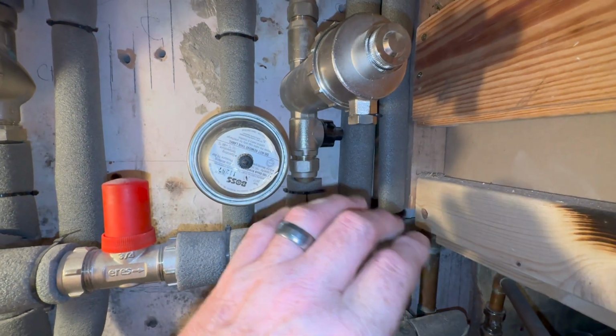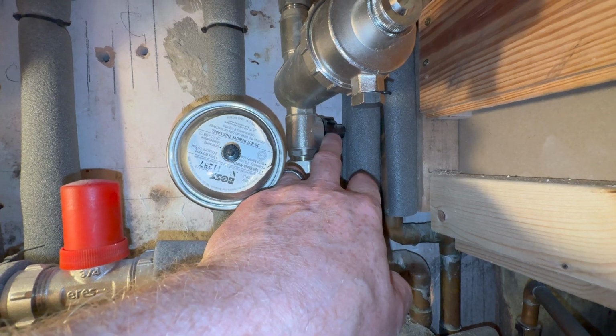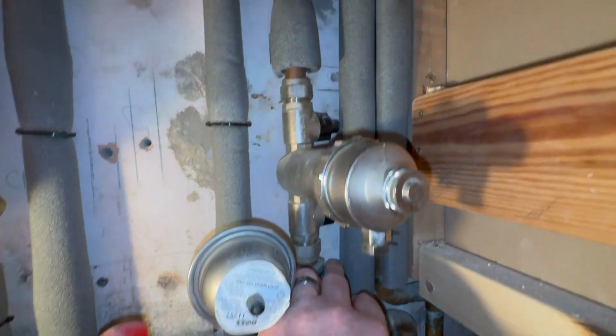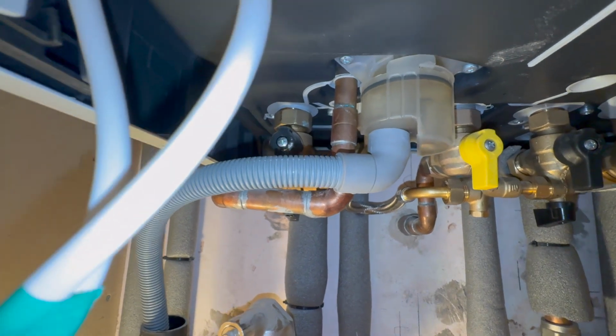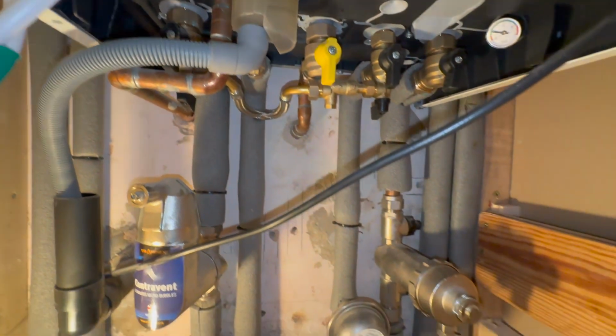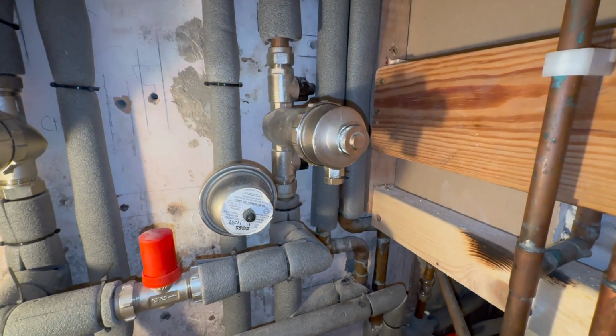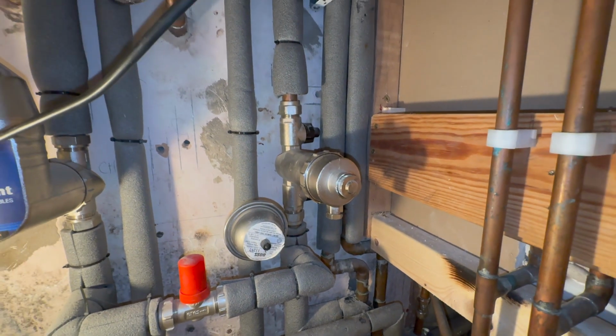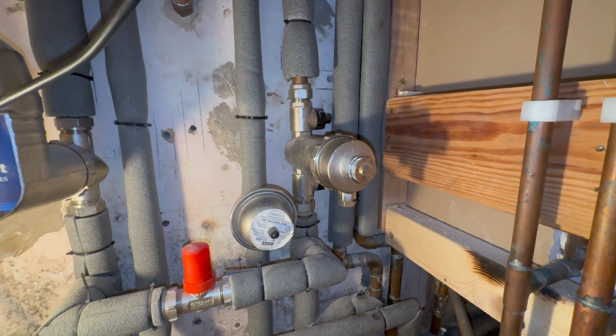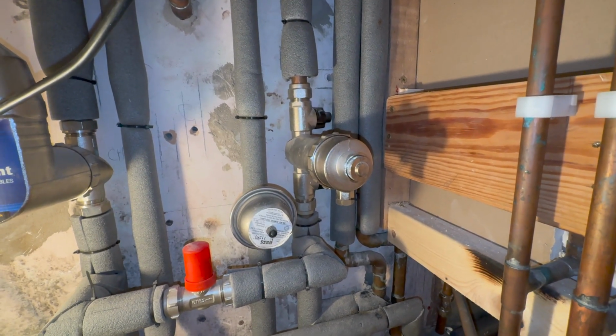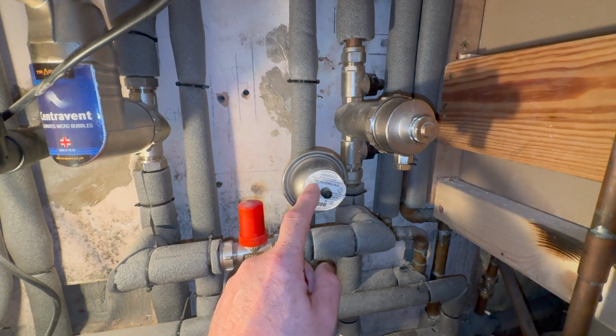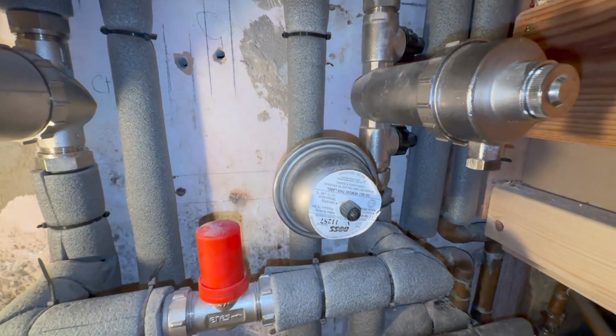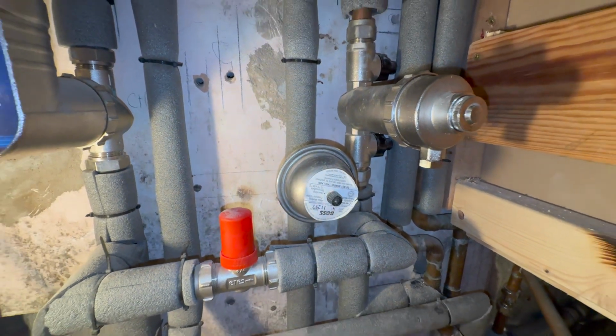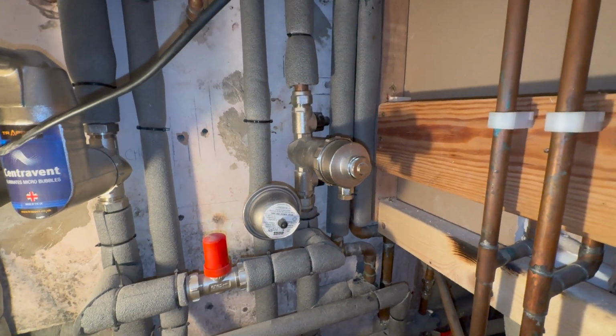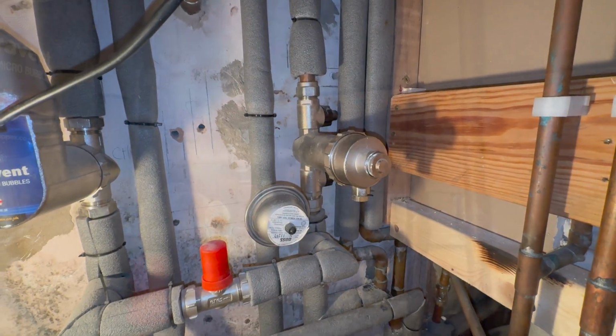Now next I'm going to check how much dirt and crud is in the magnet, but what I'm going to do is I'm just going to isolate it on this valve here and then leave that one open and then isolate it under the boiler here, and then once I've drained the water out of the magnet, it'll also drain the water out of the boiler, and then I can check the expansion vessel in the boiler, and then I can also check the pressure actually in this by isolating the water. So let's get on with that bit then.